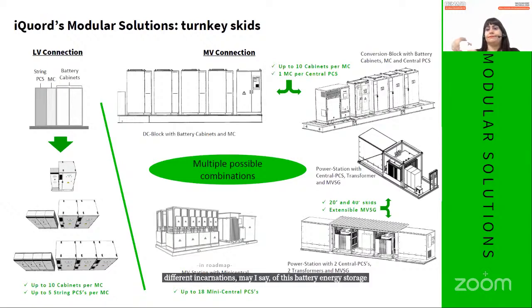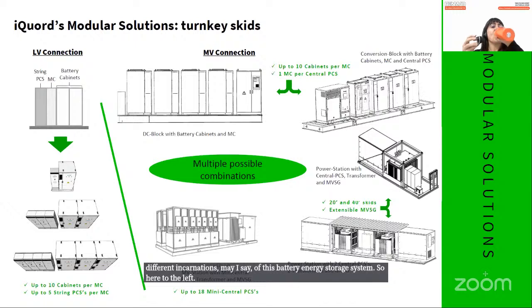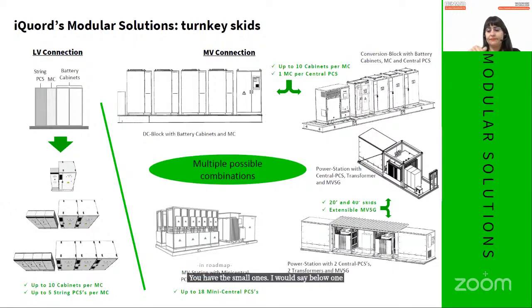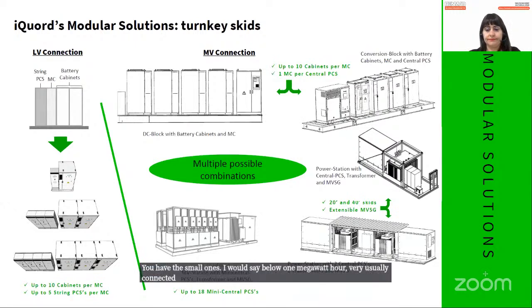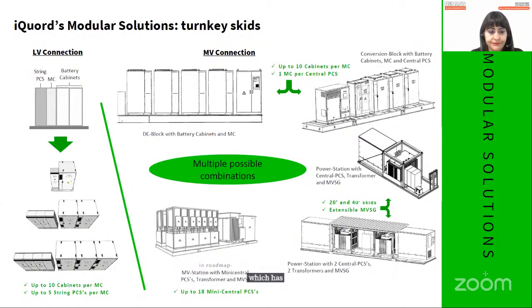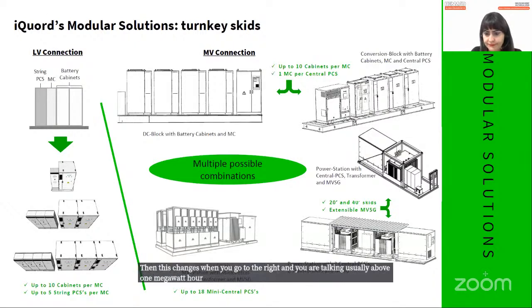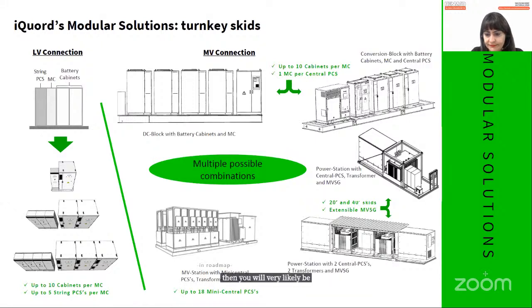To the left, you have the small ones, I would say below 1 megawatt hour, usually connected in low voltage. We use this small PCS, which has a direct output at 400 volts AC, so you do not need a transformer. This changes when you go to the right, talking usually above 1 megawatt hour capacity installed, where you will likely connect to medium and high voltages, so you will need a transformer and medium voltage switchgear.